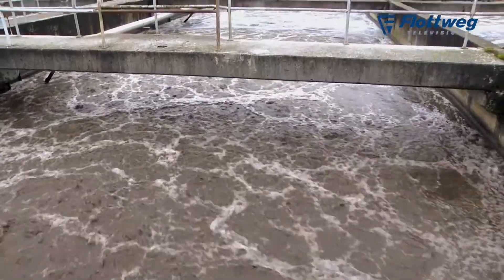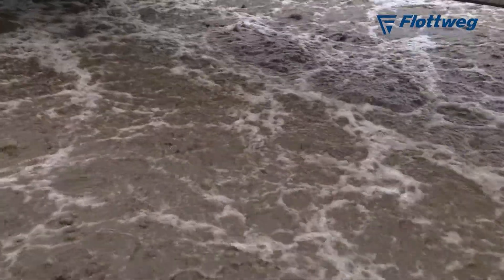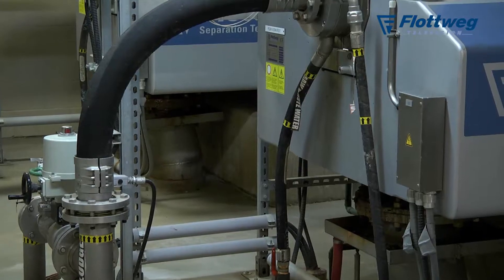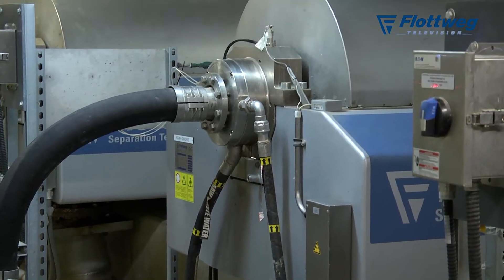Through the normal course of wastewater treatment, there is sludge that is produced and these sludges need to be disposed of, and our disposal process is incineration. We utilize the Flottweg centrifuges to de-water our sludges to a solids content of about 26 percent.